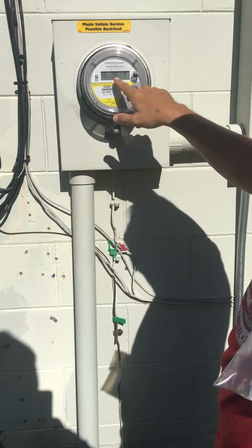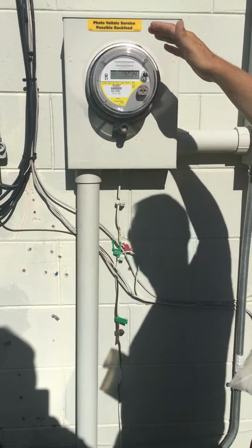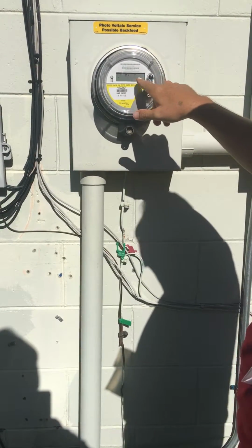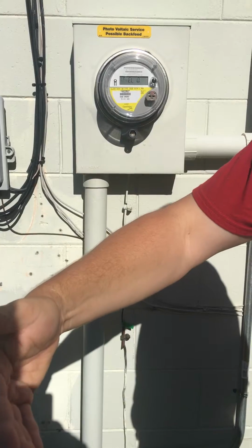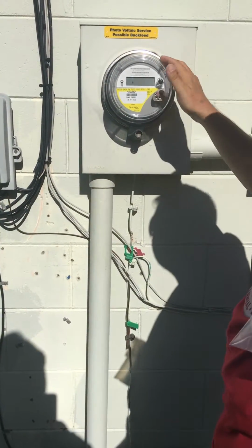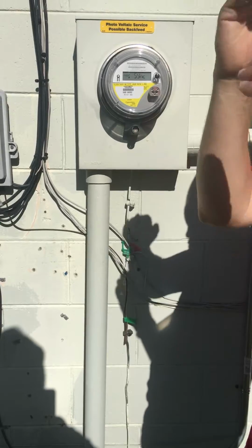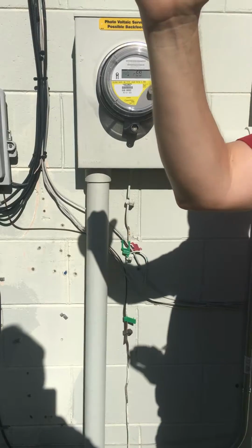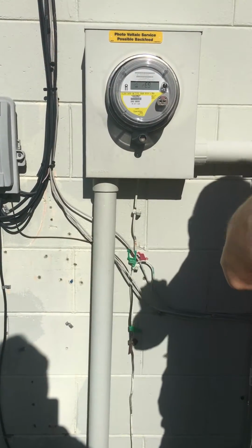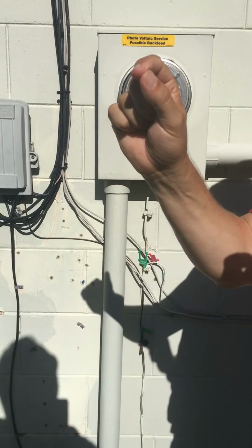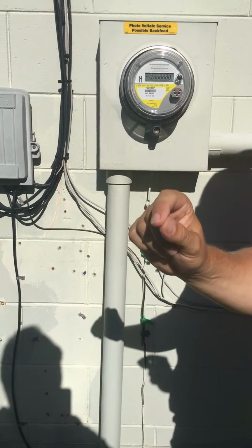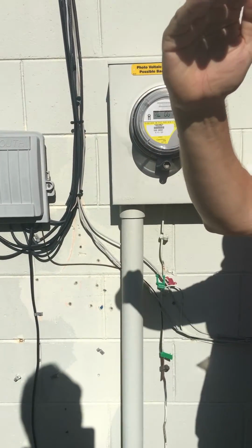That screen has the number of kilowatt hours that this meter shows that I've purchased over the life of the system. The 01 screen is the amount of energy that I've sold over the life of the system. Duke Energy will come and read the meter once a month, and they'll read those two numbers, and on the bill they'll say, okay, what was it last month? They take the number this month, the number last month, subtract it, and that's the energy you're billed for, or the energy that you have as credit. On that bill, it's how much energy you purchased minus how much energy you sold, and you pay the net.